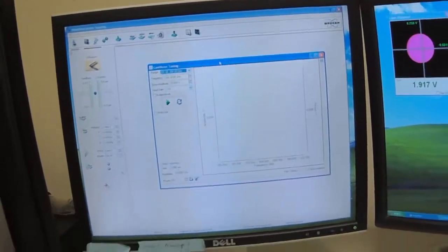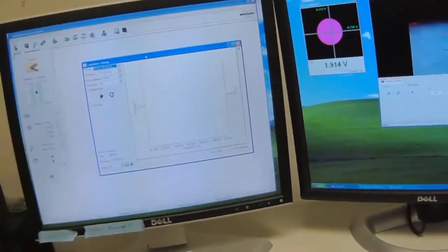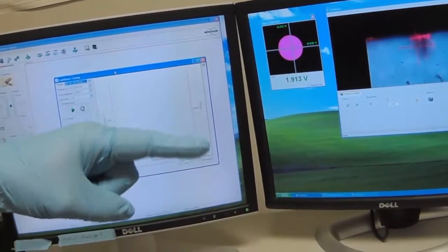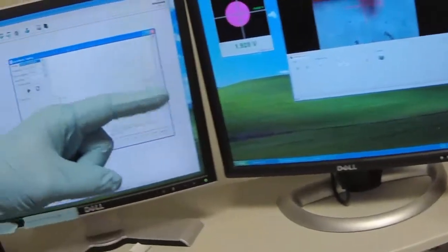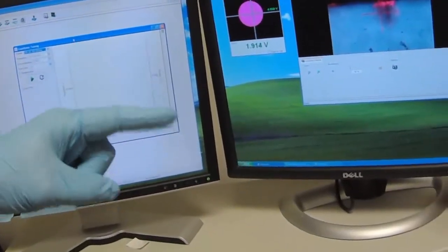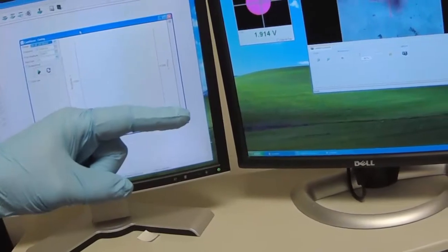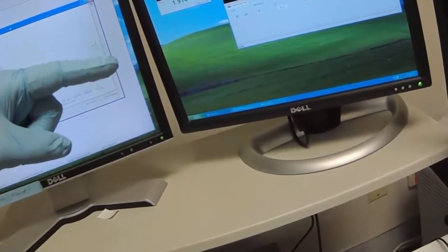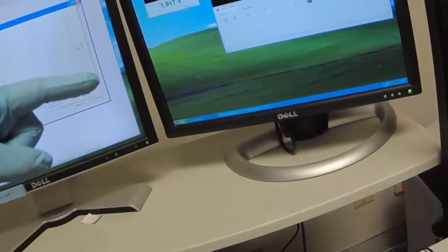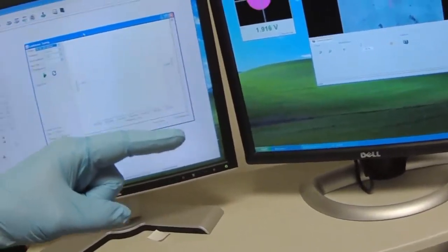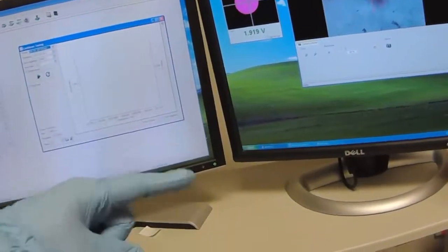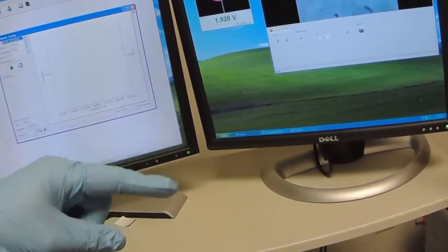Before we engage the surface, we want to tune the cantilever. We're working in tapping mode, which means that the cantilever is going to be vibrating. And just like any vibrating object, it has a resonant frequency. So we want to find what is the resonant frequency of this cantilever so that if we drive the vibration to that resonant frequency, it will have the optimal sensitivity. And we call it tuning, and it's like a tuning fork, which is kind of what we're doing. We're adding some energy to the cantilever and seeing how it vibrates naturally.